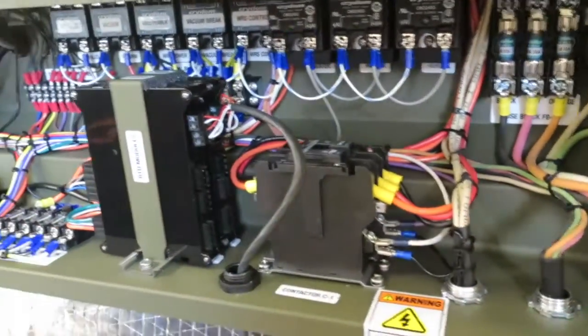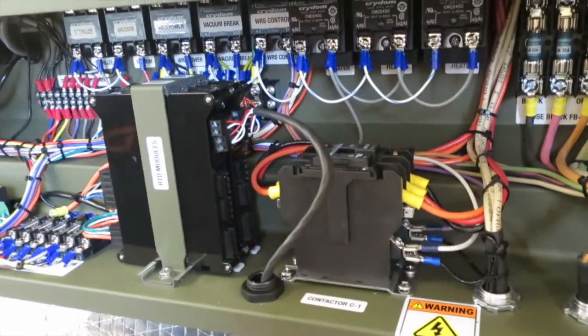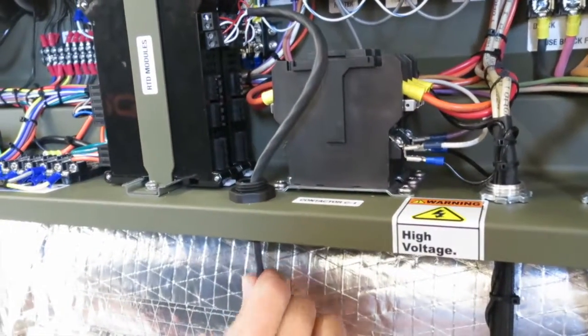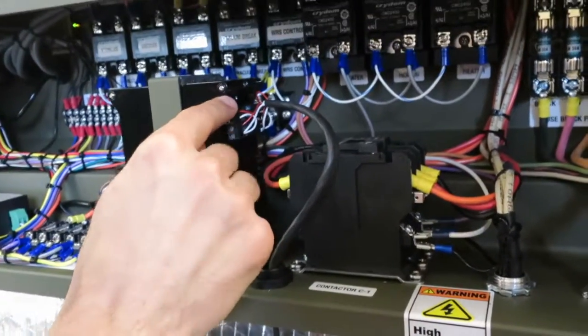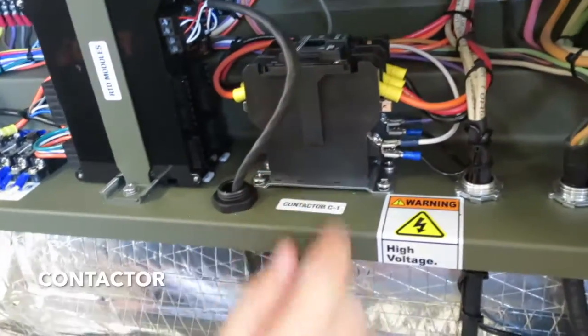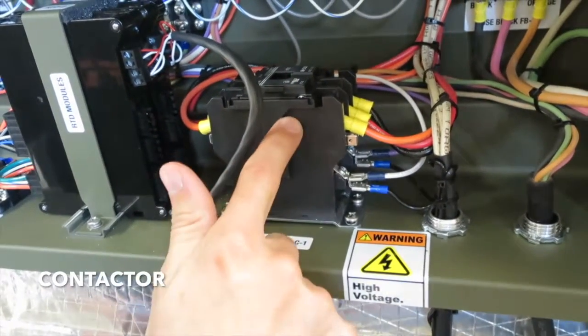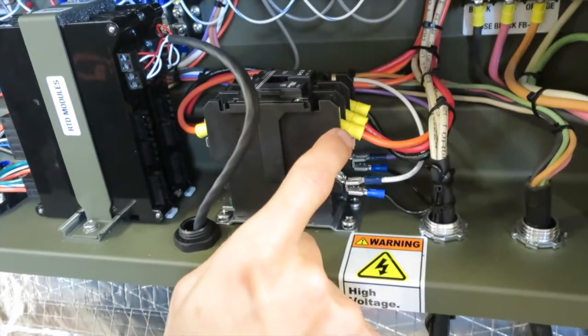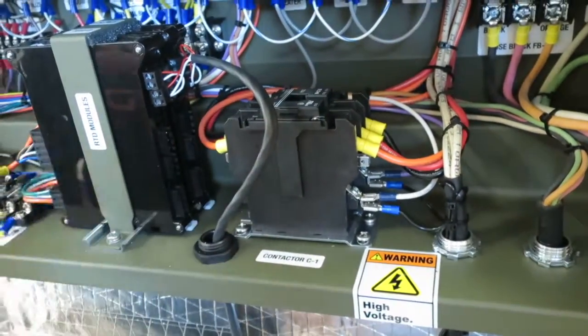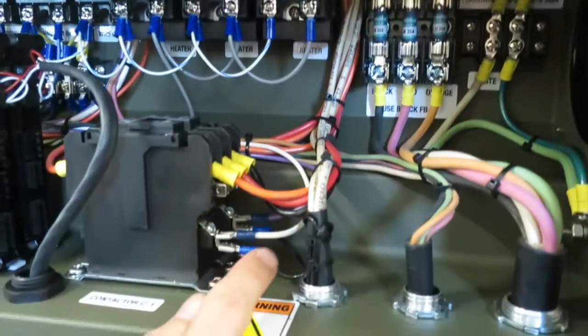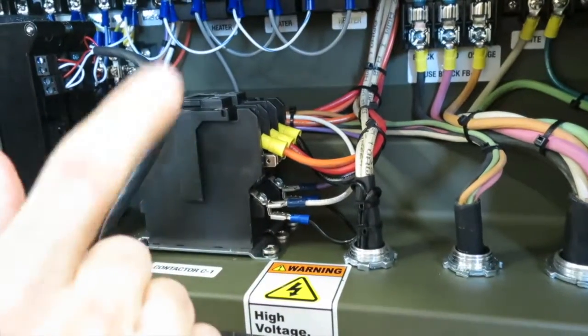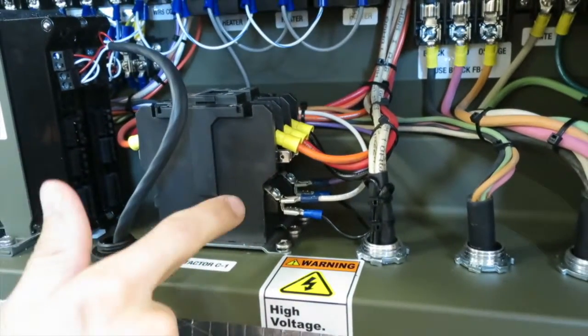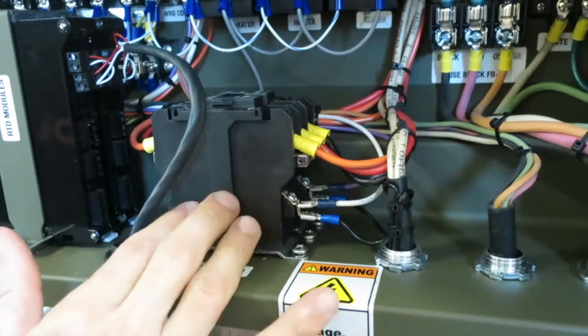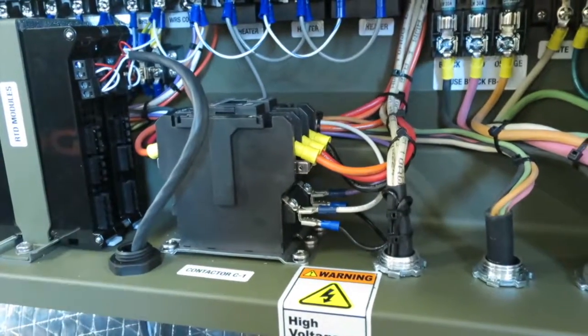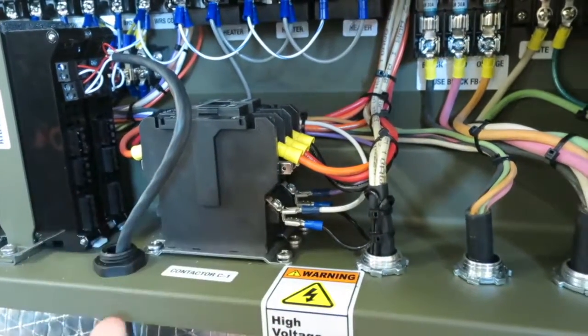Again, this is the cable coming from your RTD probe. You have a little cord grip here just to keep it nice and tight. So if anybody's messing with it, it won't come loose from the transmitters. Alright, right here we have the contactor. The label says contactor C1. On the right side, I have incoming power. And on the left side, I have power that's going to the rest of the unit. Right here, this white and purple wire actually go to the on and off switch. So when you turn that switch on, that is what is mechanically moving this contactor and supplying power to the sterilizer. So that's the contactor. Whenever you hear that click when you first turn the sterilizer on, that's this contactor moving.